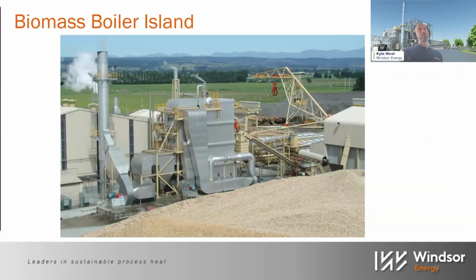And then moving on to the biomass boiler island. So boiler island consists of a fuel bin, a combustion bed, furnace walls, boiler bank, steam drum, mud drum, economizer, recuperator, and particulate control. Then there's usually an induced draft fan followed by a flue stack.